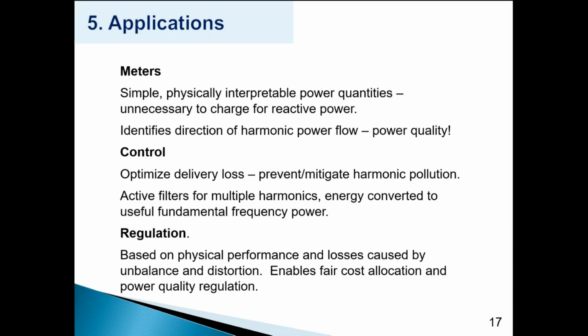And finally, or not quite finally, the implications of the first two are that it changes our electricity regulation. So based on physical performance and losses caused by unbalance and distortion, the regulator has to start saying, this sort of tariff is acceptable, this sort of cost allocation is acceptable, and this sort of power quality regulation is acceptable. And our regulator is a long way from doing any of that. So are many other regulators in the world.